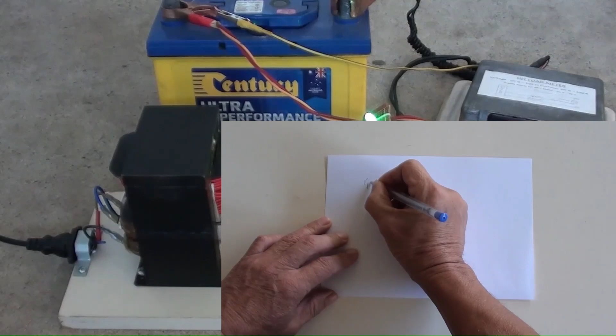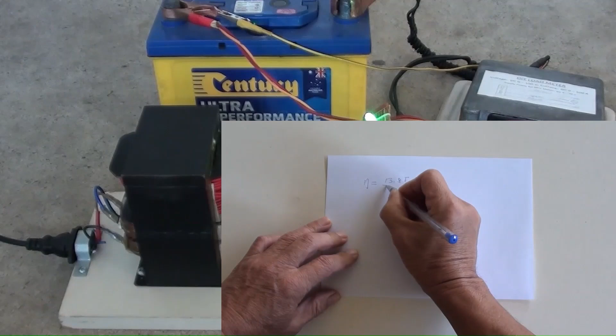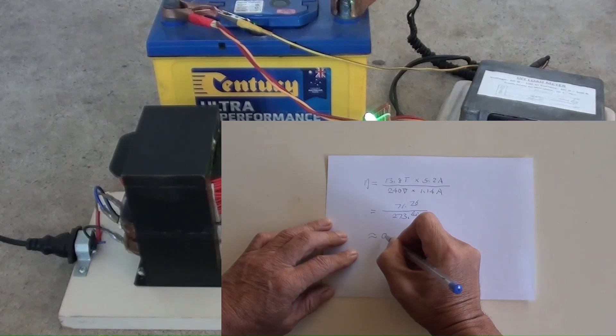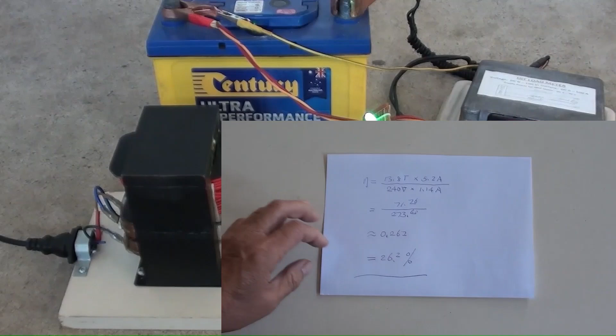So the efficiency of the power consumption equals DC voltage of 13.8 volts times current of 5.2 amperes, over AC 240 volts times 1.14 amperes, equals 71.76 over 273.60, equals approximately 0.262, equals 26.2%.